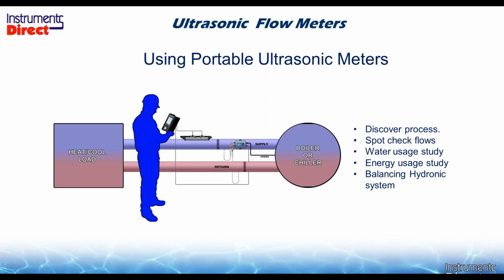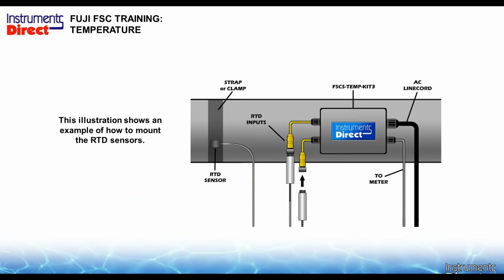The equation is flow and differential temperature. So we don't really care what the actual flow or temperature is. We actually care what the differential is between the supply and the return. So if you get over that fact, this will be a very accurate system, and you can get the kind of numbers that you're hoping to get with a clamp-on ultrasonic flow meter system. So with a portable device or a dedicated device, you can clamp on, collect your information for an energy study, balance the loop, and move forward.